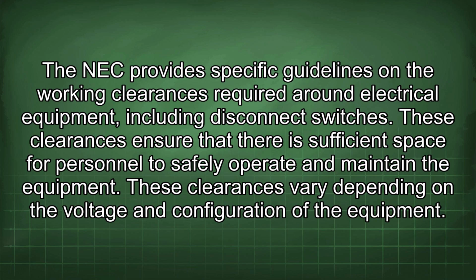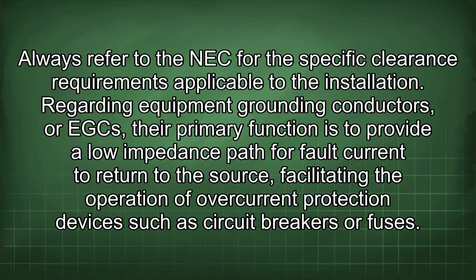The NEC provides specific guidelines on the working clearances required around electrical equipment, including disconnect switches. These clearances ensure that there is sufficient space for personnel to safely operate and maintain the equipment. These clearances vary depending on the voltage and configuration of the equipment. Always refer to the NEC for the specific clearance requirements applicable to the installation.